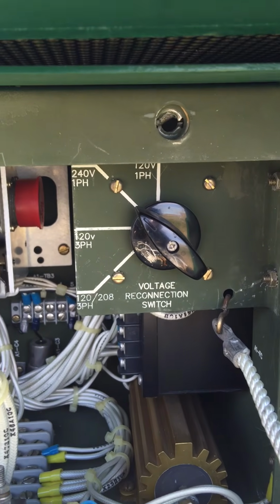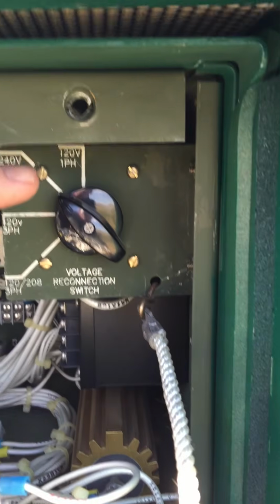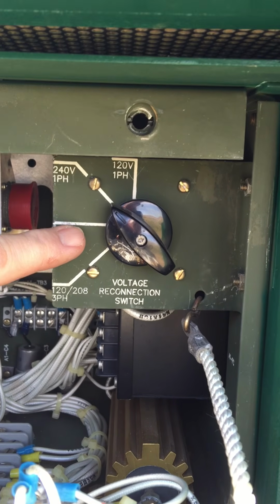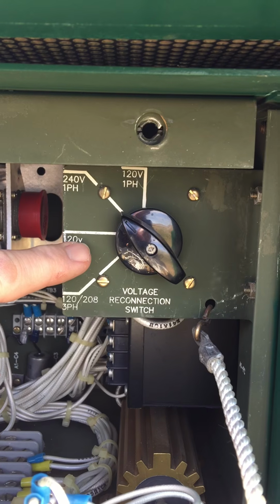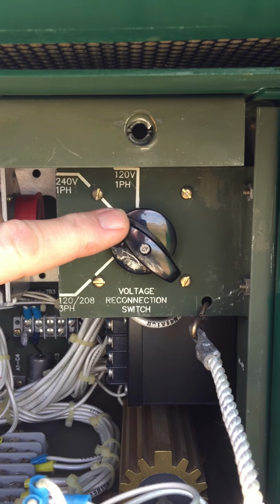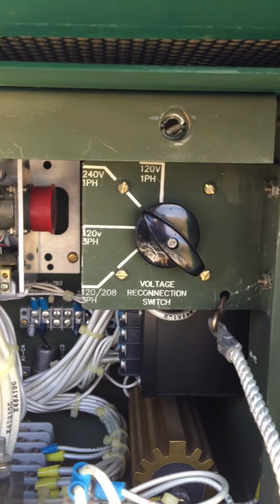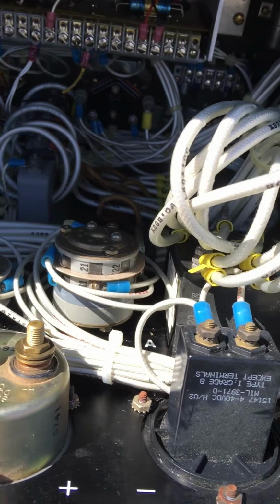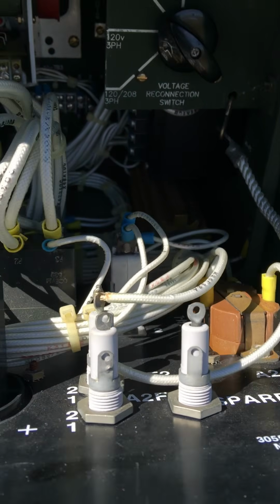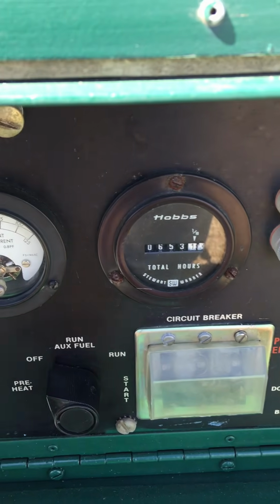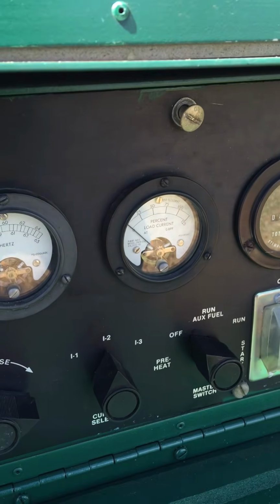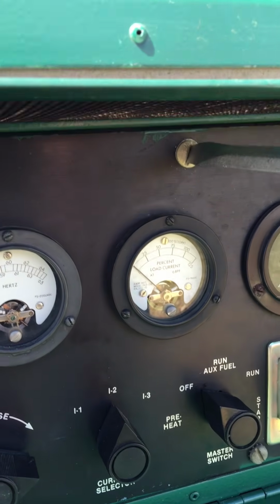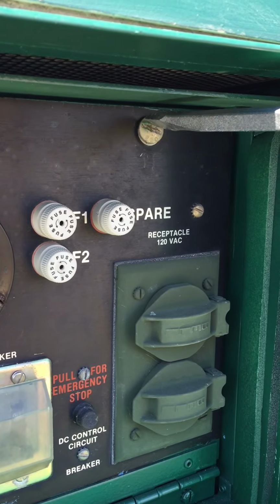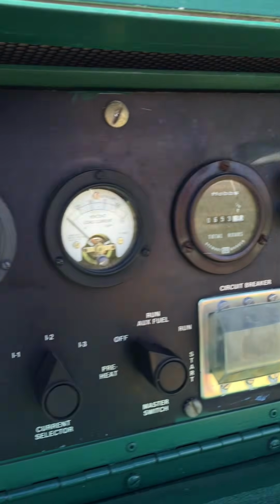There is your voltage reconnection switch. As you can see, I have it set on 240 for the load bank. Do not move this switch while the set is running to change between phases. You'll damage your set. Pull back. You can see the wiring on the back side of the meters, and everything's real clean, nice shape. Close this back up. Bear with me. I want to fasten the fasteners back so that when the set starts, the door will be good and closed.